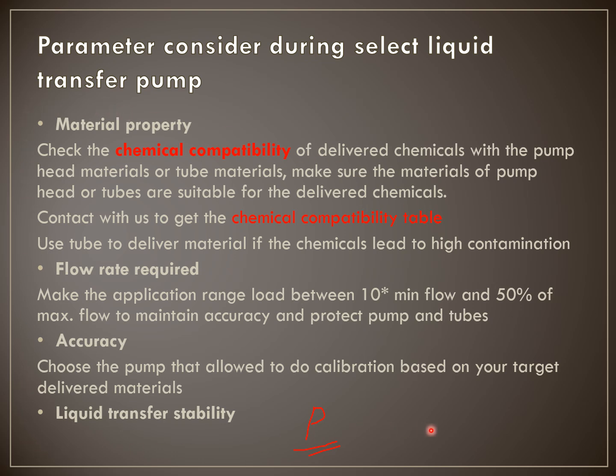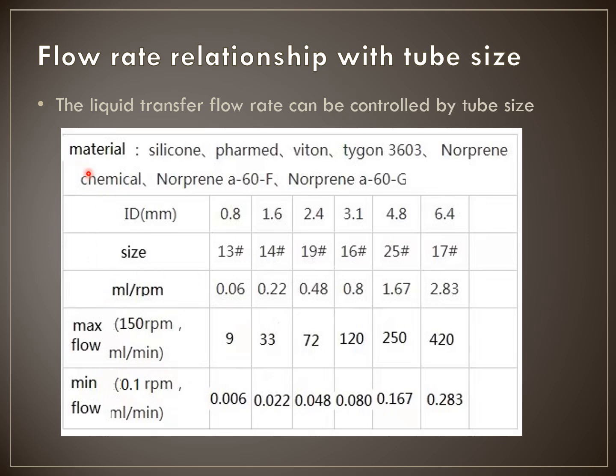With consideration of these parameters, you can find a suitable pump for yourself. There is a table we recommend when selecting a peristaltic pump. Pay attention to the step speed in milliliters per step per minute, which is related to the resolution of your pump. When you require higher accuracy or your transfer amount is very small, you need a higher resolution. Also check the minimum flow the pump can transfer — make sure your target minimum flow is at least 10 times the pump minimum to maintain accuracy.